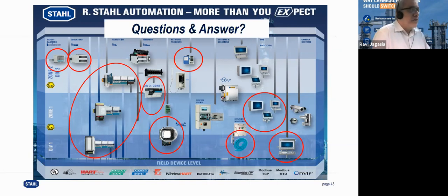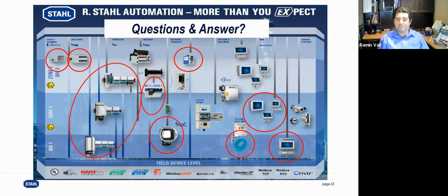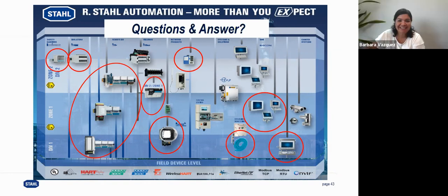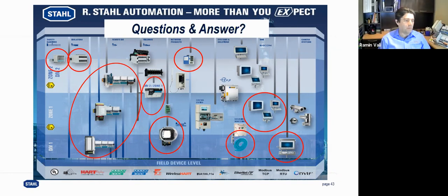And then there is one more question here, which is, what is the difference between optical and galvanic isolation? Barbara, you can take it up. Can you help me with that one, Ramin? Sure. We have some associated apparatus which use photoelectric or fiber optic type or optical type isolation. What we see is that transformer isolation, like galvanic isolation, always provides a better level of protection. They can go up to 1500 volts or 2500 volts, but optic or fiber optic or photoelectric or phototransistors can only go up to 500 volts or 750 volts isolation. So the level of isolation is different.